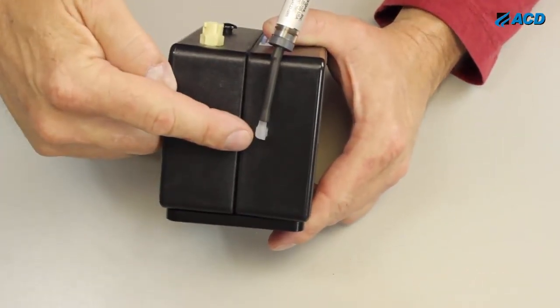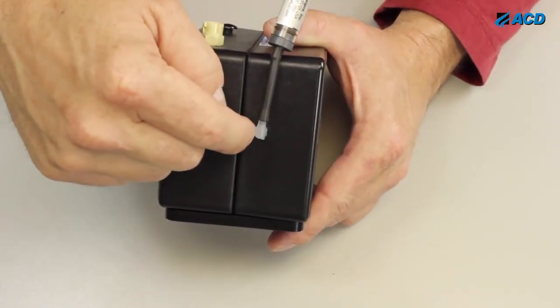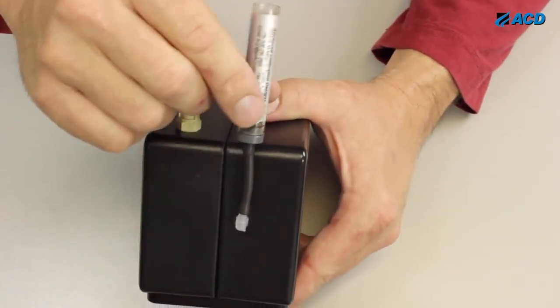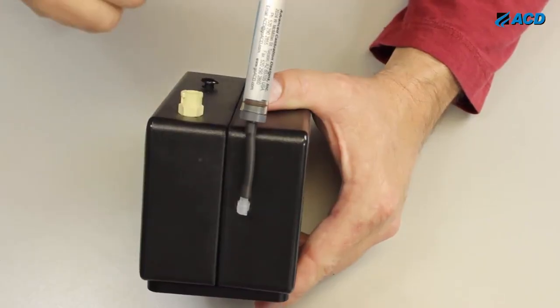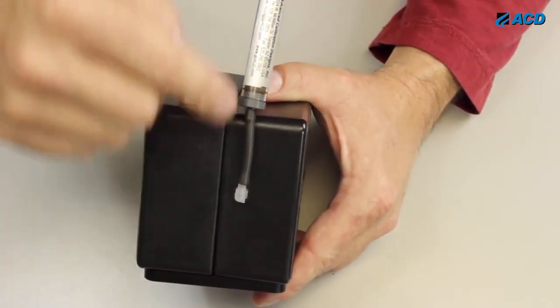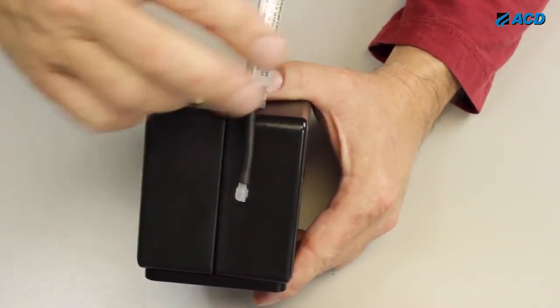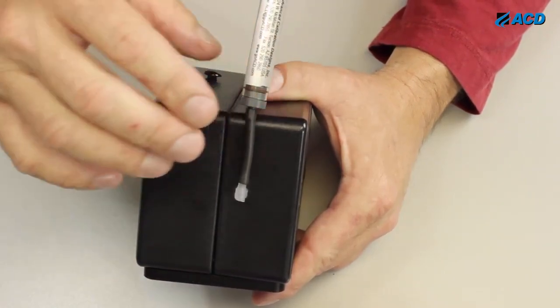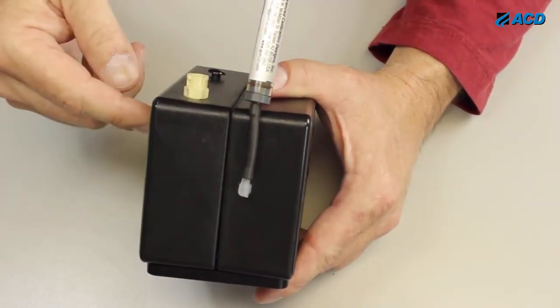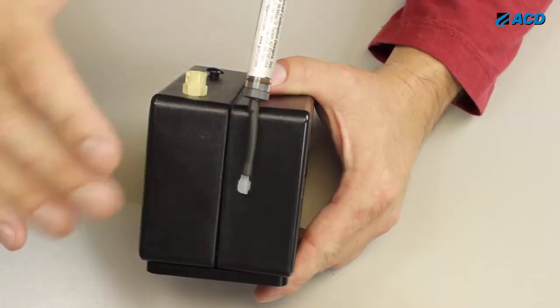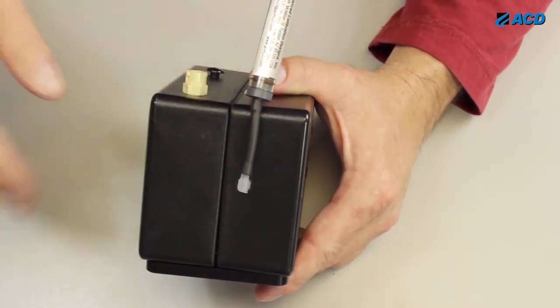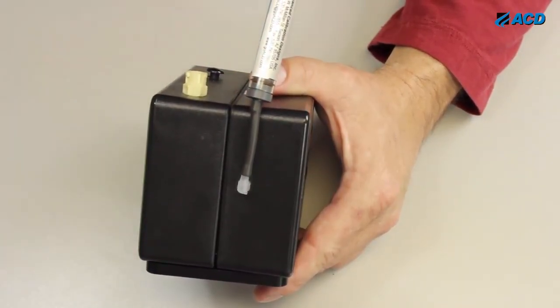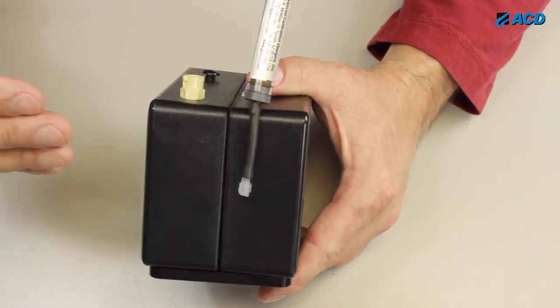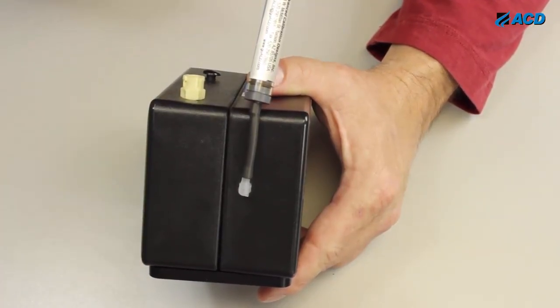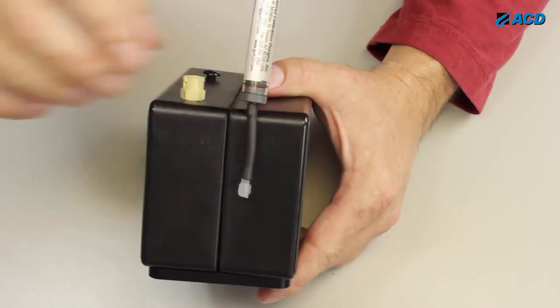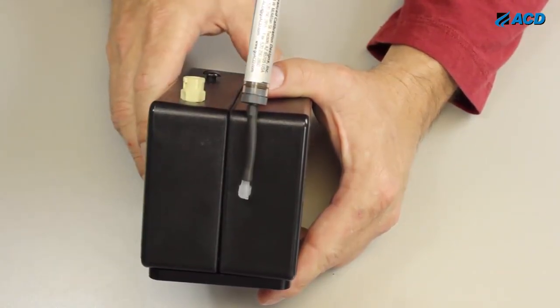This is the fresh air intake, so the air comes into the unit through this spot here. Here we have attached a charcoal filter so that we ensure that fresh air is coming in. If you have a clean background and you know it, you don't need these. If you may have dirty background air, in this case we have a chlorine generator, if there might be chlorine in the air, you want to eliminate that because it will add to our calibration gas. So if there was 1 ppm chlorine in this room and you turned it on to 5, you'd be getting 6 out. So this charcoal filter ensures that that doesn't happen.